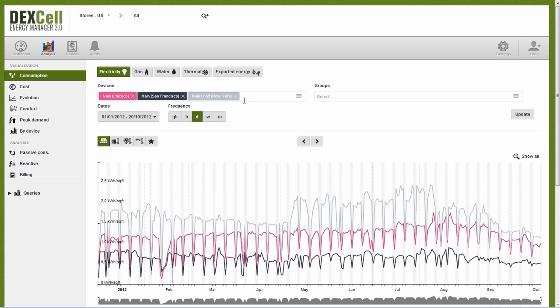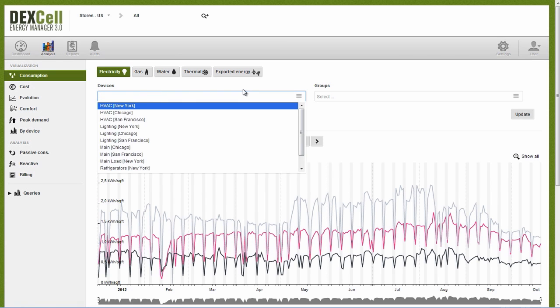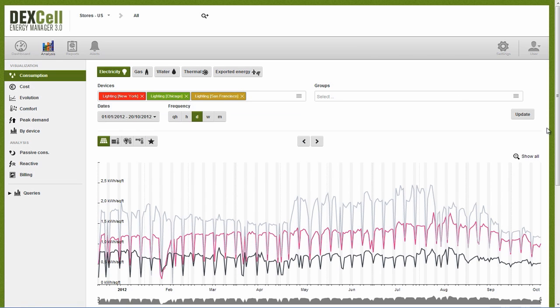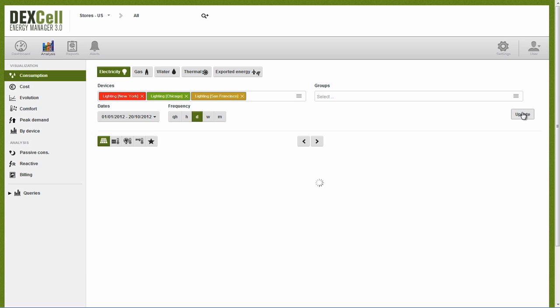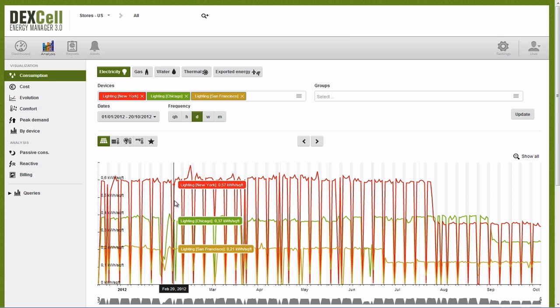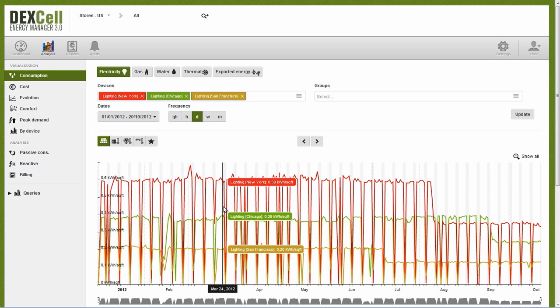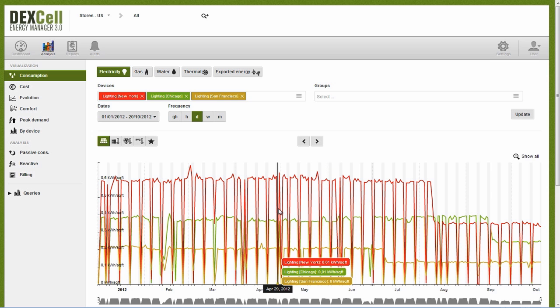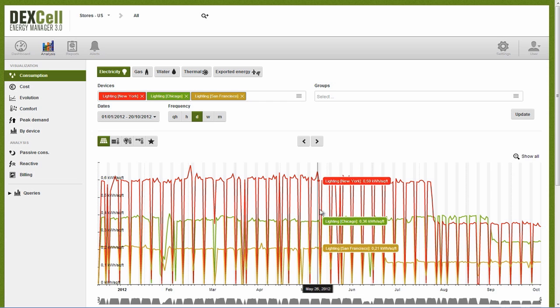Let's repeat the analysis, but this time focusing on the lighting systems in particular. First, we'll select three lighting meters and compare their yearly consumption. When we control our results for surface area, we see that from the beginning of the year up until August, the New York store averaged a consumption of 0.6 kilowatt hour per square feet, which is higher than that of Chicago at 0.37 kilowatt hour per square feet, and much higher than the San Francisco store's consumption at only 0.2 kilowatt hour per square feet.